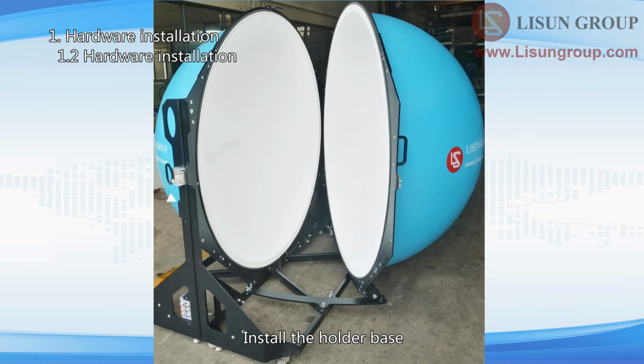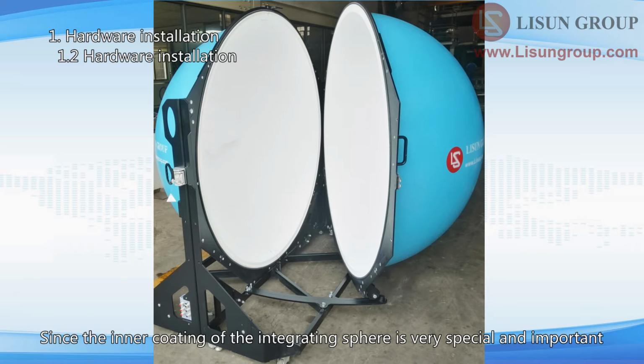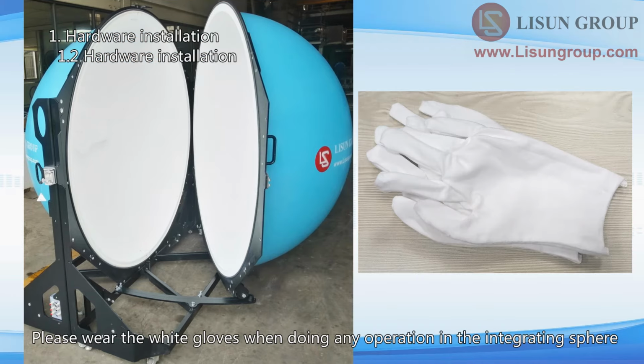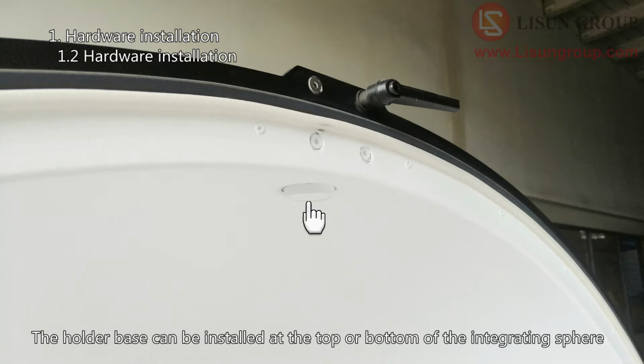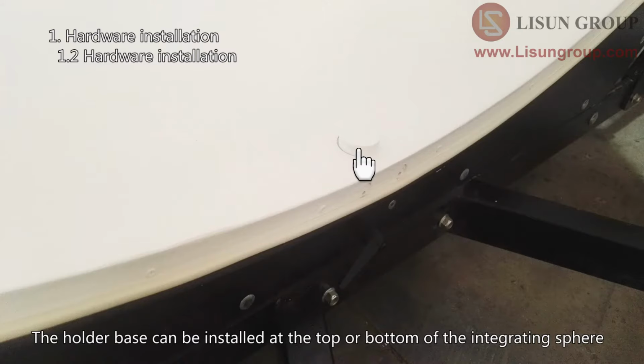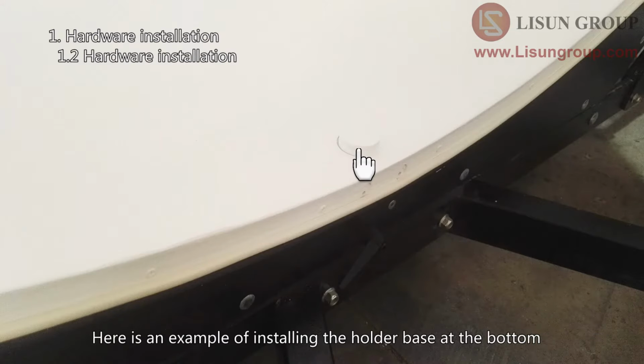Install the holder base. Since the inner coating of the integrating sphere is very special and important, please wear white gloves when doing any operation in the integrating sphere. The holder base can be installed at the top or bottom of the integrating sphere. Here is an example of installing the holder base at the bottom.